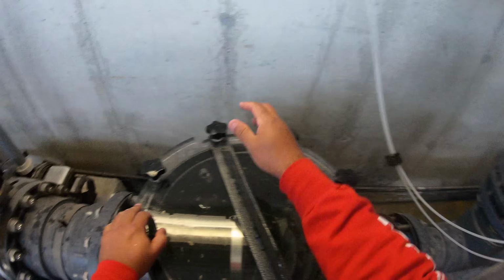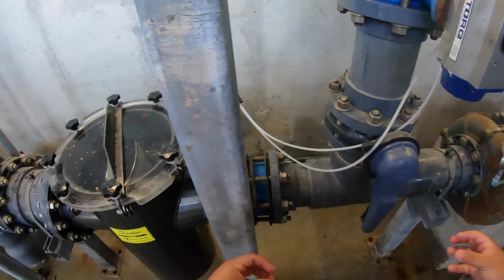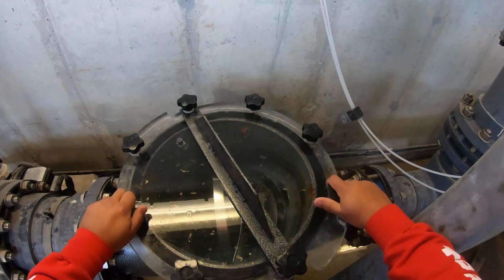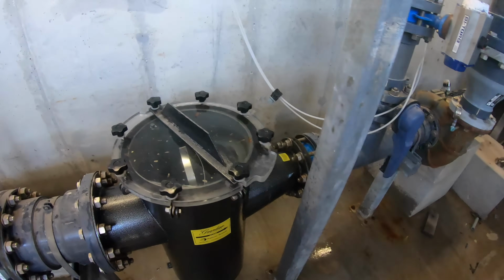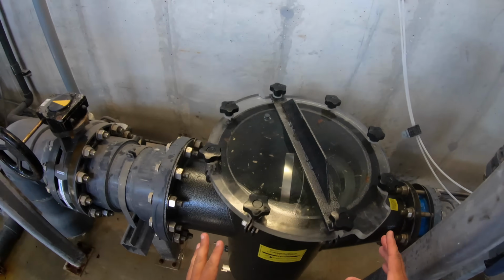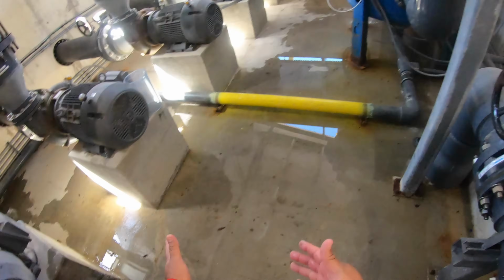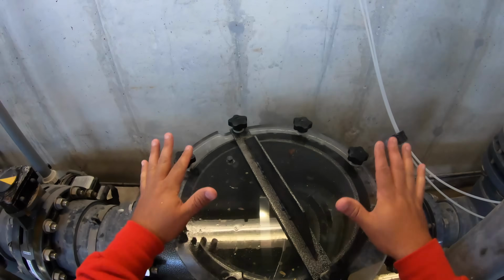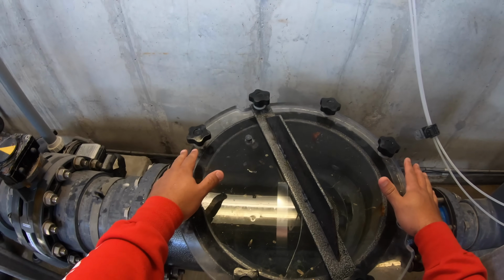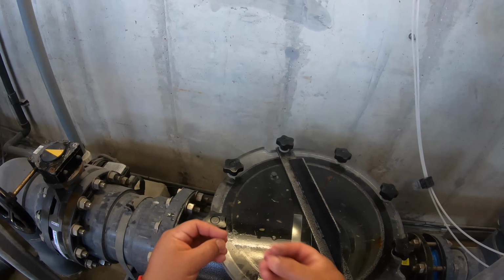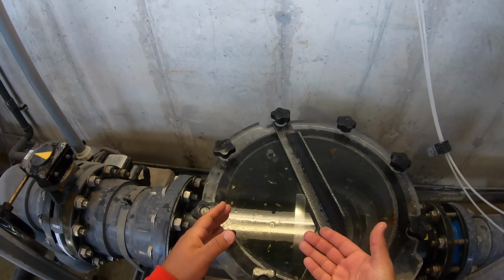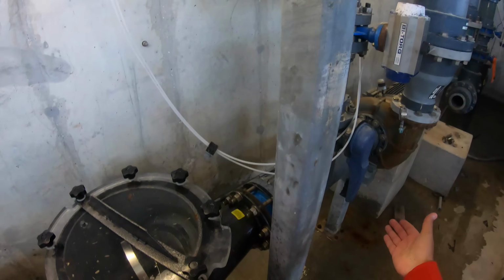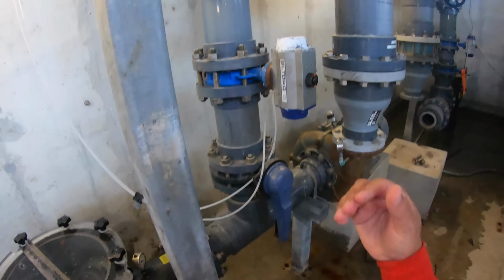And now what's happening is there's a little bit of suction, so I can tighten the basket down a little bit more if I need to keep it from leaking. And there's two reasons why we want to do that. Yeah, it's just water, and of course I spilled water on the floor, but if we don't keep the lid nice and tight, what could happen over time if there's an air leak and we do have some heavy suction, it's going to pull air into the basket and at some point pull into the pump, and we don't want that.